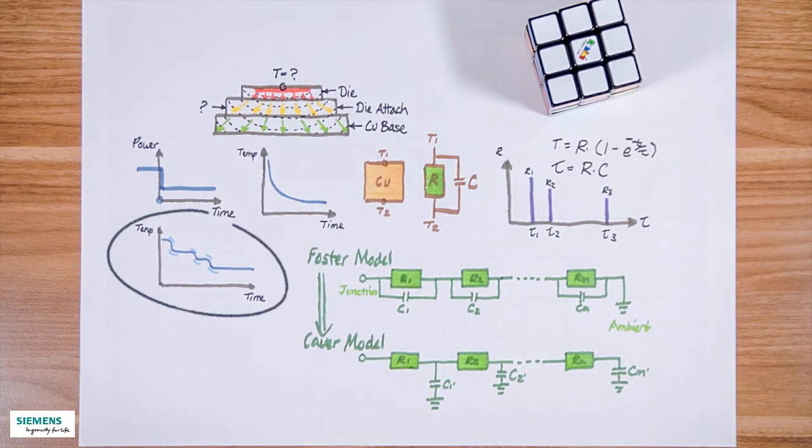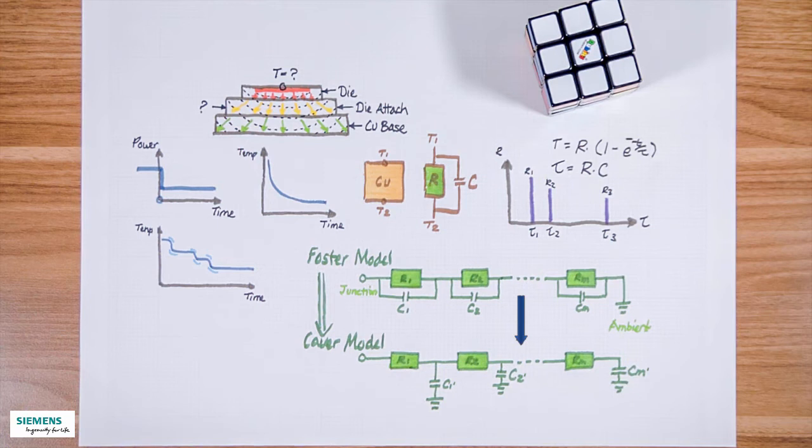To recap, we measure this curve, then we break down the curve to a number of R's and C's. Then we do a mathematical transformation from a so-called Foster-type thermal model to a ladder-shaped Cauer model.